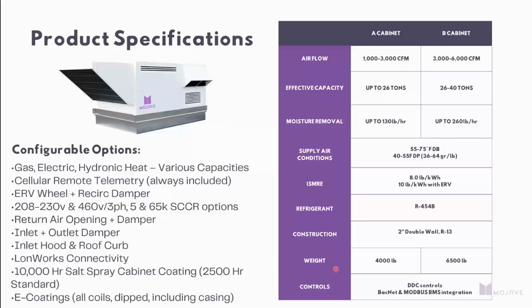Hardware-wise, we have 2 cabinets currently, a 1 to 3,000 CFM cabinet, as well as a 3,000 to 6,000 CFM cabinet. We are already using 454B refrigerant, that new A2L refrigerant. This is a variable speed driven system, so variable speed compressor. It is an inverter compressor, not a digital scroll product. We are using ECM supply fans capable of 3 inches external static, as well as regen fan and condenser fan are AC with VFD driven. Double wall construction, foam injected panels, R13 insulation.